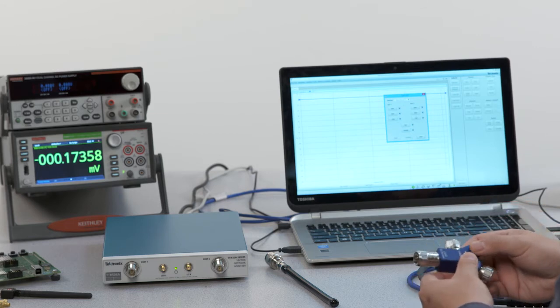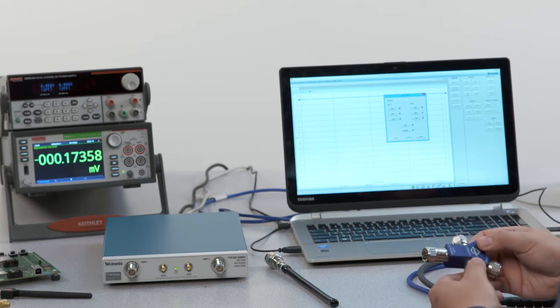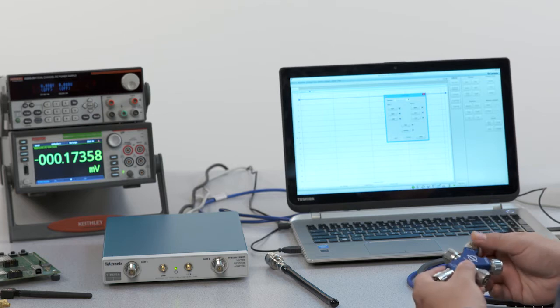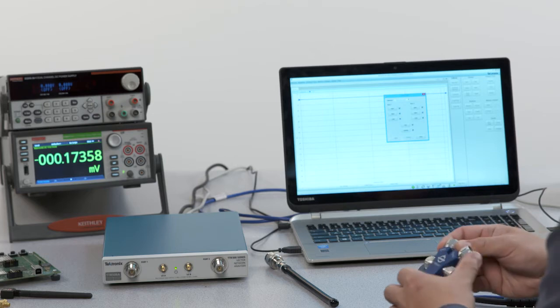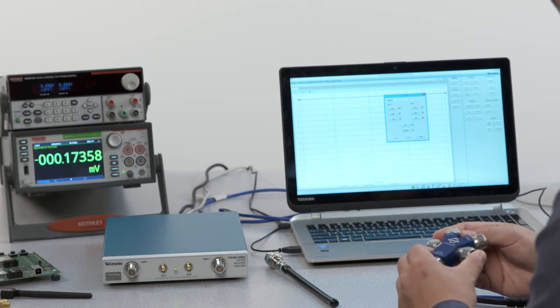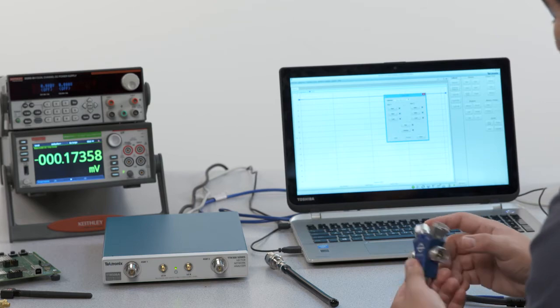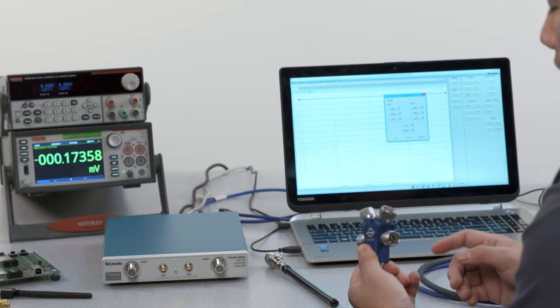So now we begin. We're going to start with port 1 and we're going to do an open short load cal. We're going to repeat the procedure for port 2 and then do it through.